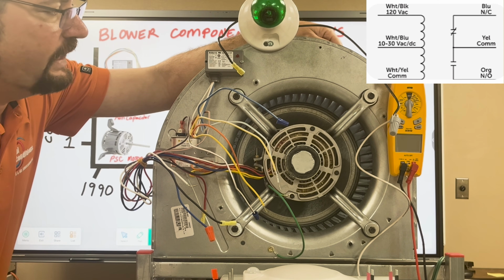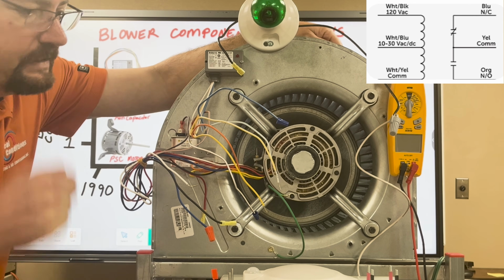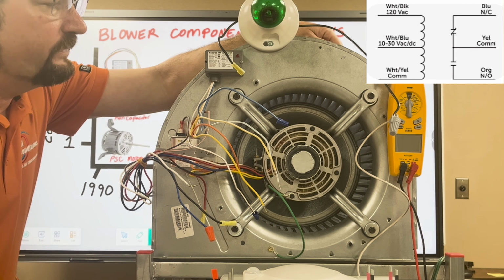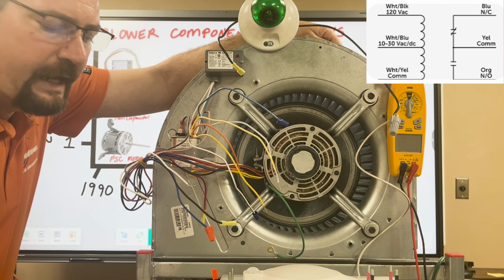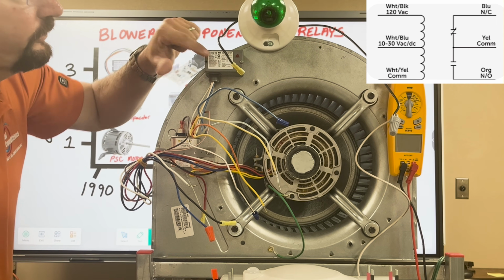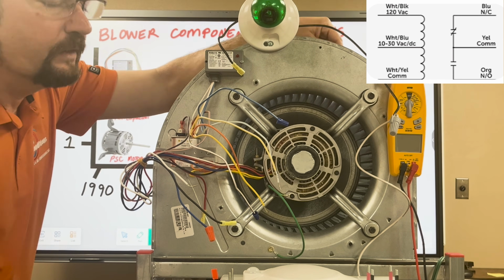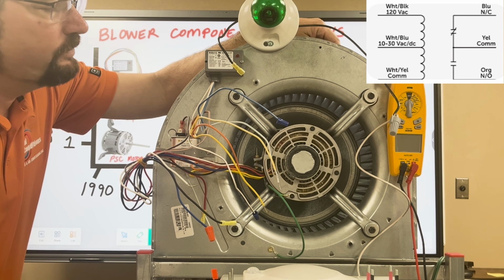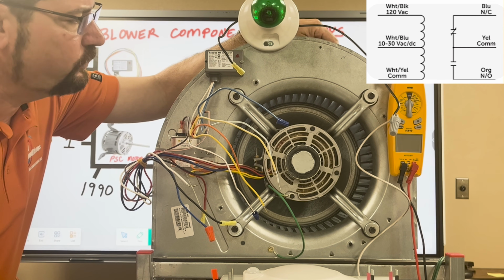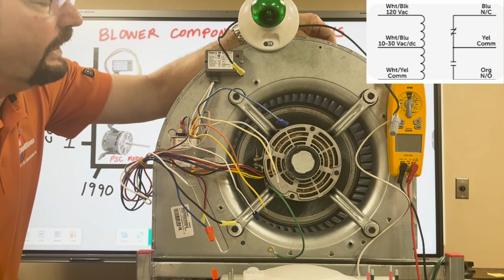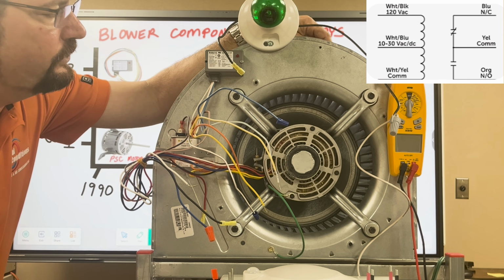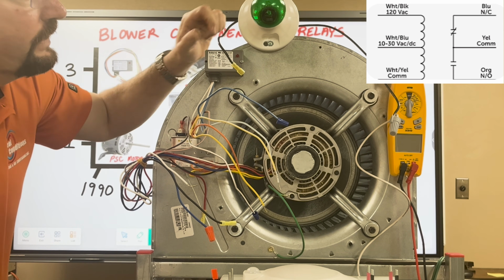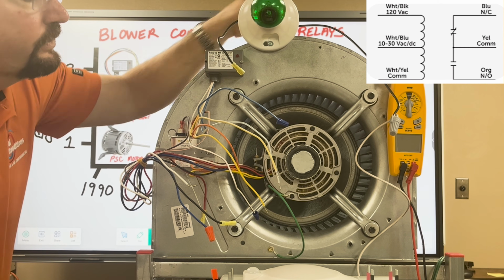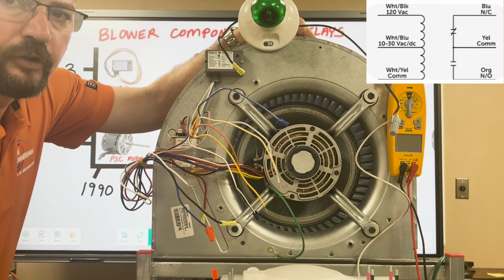Now, as far as the contact side, it doesn't matter what you use it on. The only thing you have to keep in consideration is the amount of ampacity that you can pull across the point, so you don't create any problems with too much power. This one is good for about 10 amps, and they do go up to 20 amps that I've seen. The other thing that I like about it is this little red light here. That red light is an indicator that there is coil voltage.